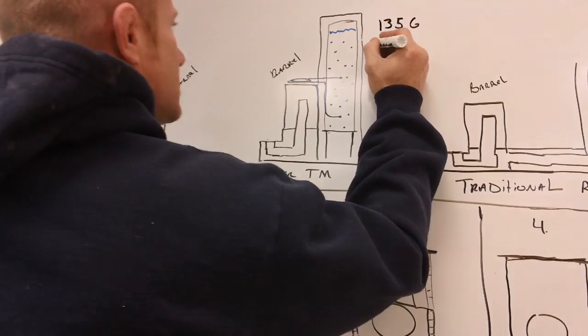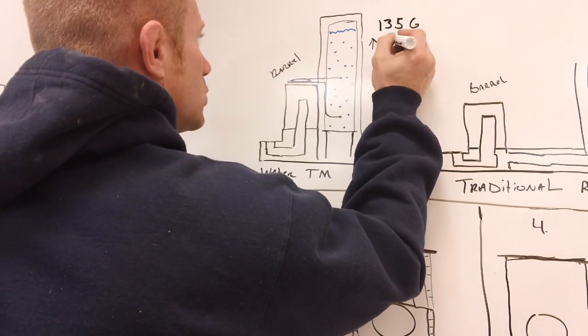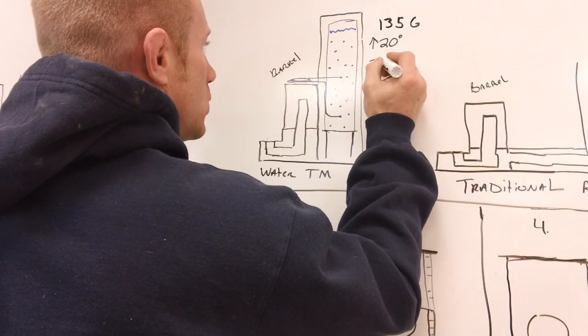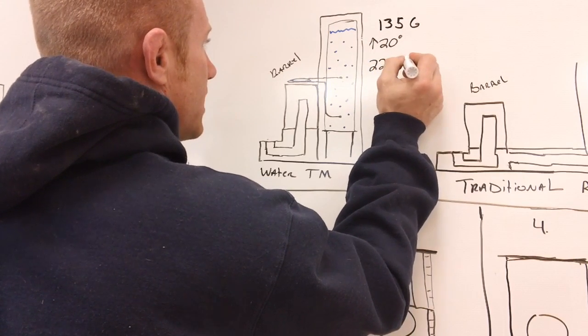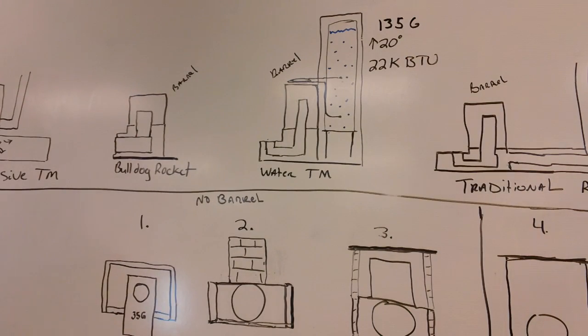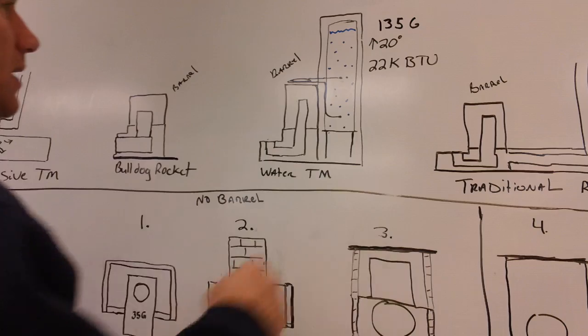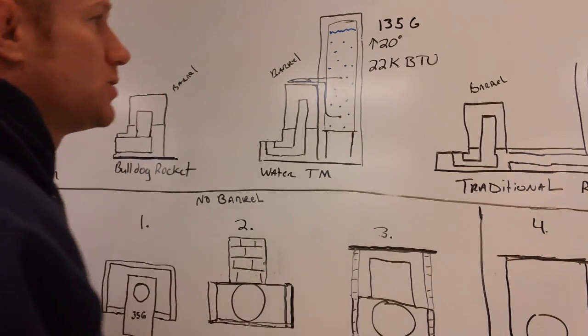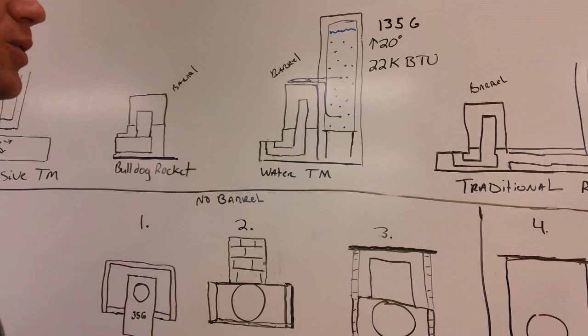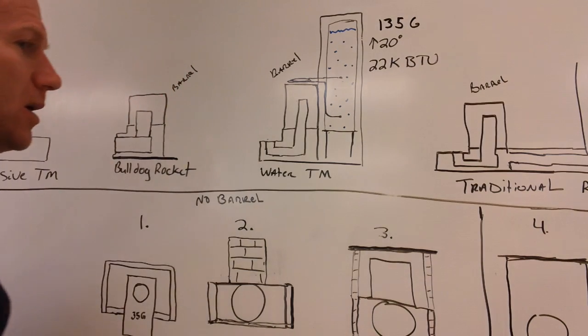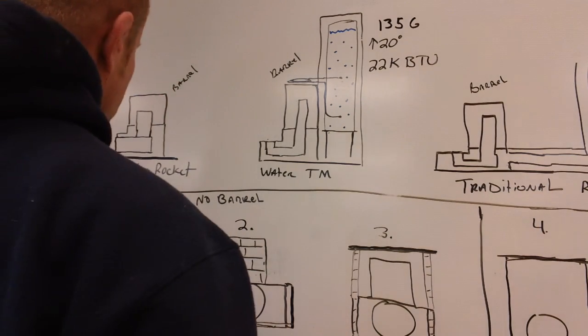If you raise 135 gallons 20 degrees, you store 22,000 BTUs. So if you've got a 250-gallon tank in here, you'd be storing pretty close to 50,000 BTUs. A 250-gallon tank is somewhere 30 inches diameter, about 6 foot tall.